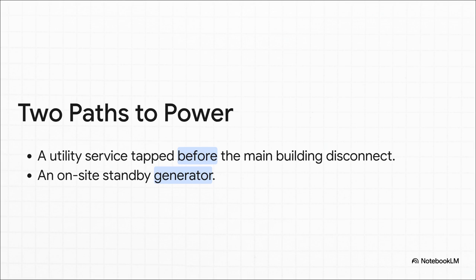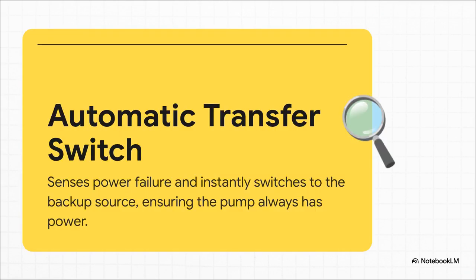The second path is an on-site standby generator, just sitting there waiting to roar to life if that utility feed ever fails. And the brain behind this whole operation, that's the automatic transfer switch, or ATS. It sits there right in the pump room, and its only job is to watch that main power line. The second it detects a problem, bam, it flips the switch over to that standby generator, usually in just a few seconds. The pump controller never even knows anything happened.